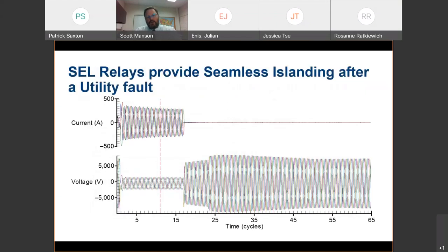Here's an example of how we use SEL programmable protective relays to isolate faults and restore service, well, really without even a loss of service. Here on the bottom on the x-axis is cycles. Now, over this entire time frame, 60 cycles is 1 second. So this is a 1 second snapshot of an event. The whole transpired event happened in about a third of a second, a blink of an eye. You won't even see this.